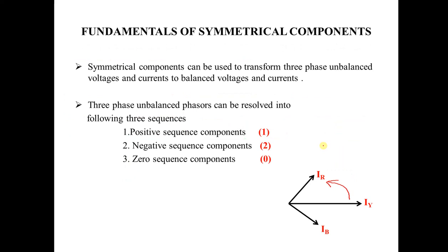Next we have to see the fundamentals of symmetrical components. Symmetrical components are used to analyse an unbalanced system of three phase currents, for example equipment where the red phase impedance differs from the yellow phase impedance. It is applicable to any three vector system whose resultant is 0, meaning symmetrical components convert three phase unbalanced voltage and current to balanced voltage and current.